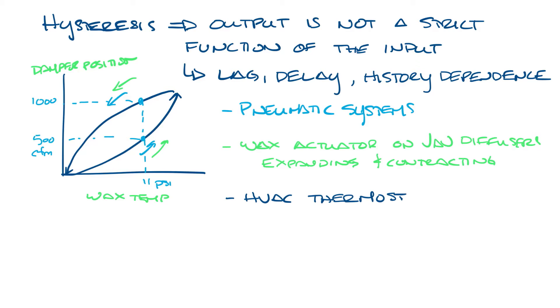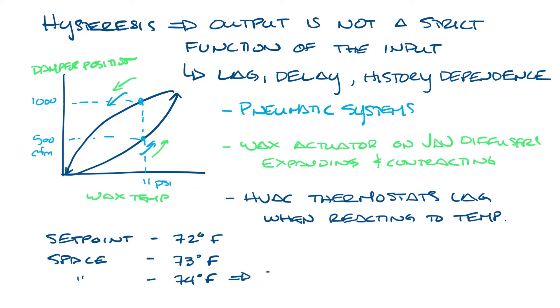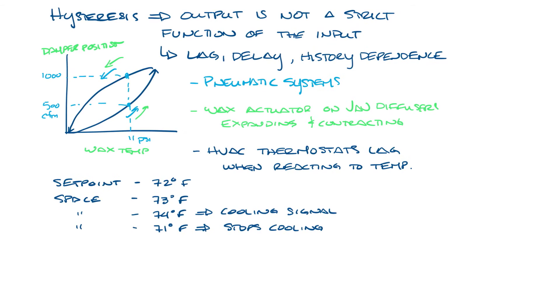And another place we see hysteresis is in thermostats that use a lag in reacting to space temperature. For instance, let's say that the setpoint is 72 degrees and the space temperature is 73 degrees. It may not send a cooling signal until it gets to 74 degrees, and it may keep cooling the space until it gets to 71 degrees. So there's a delay from the 72 degrees to the 73 degrees before it even sends a cooling signal.